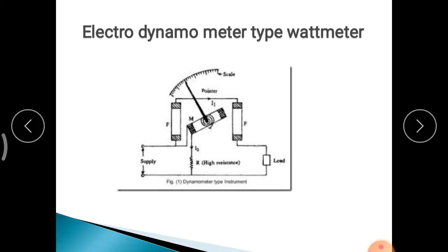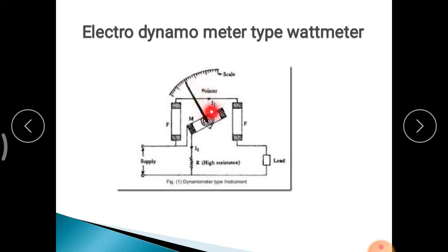Regarding the working: it operates on the motor working principle. Whenever a current-carrying coil is placed in a magnetic field, a force is exerted on it. When the current-carrying moving coil is placed in the magnetic field produced by the current-carrying fixed coil, a force is exerted on the coil sides of the moving coil, producing a deflection torque, and the moving coil deflects. The pointer attached to the spindle moves over the graduated scale and comes to rest when the deflecting torque and the controlling torque become equal.